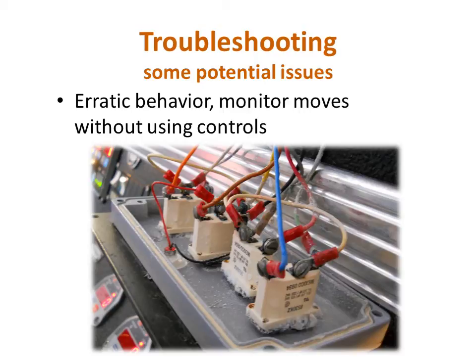There is evidence of significant leakage and corrosion to the control switches on the inside of the control box shown here. The same thing can happen with the logic box. It is also possible that a switch has gone bad or worn out, and this can be confirmed by use of a multimeter on the appropriate switch input pins in the logic board and checking either for voltage or continuity.